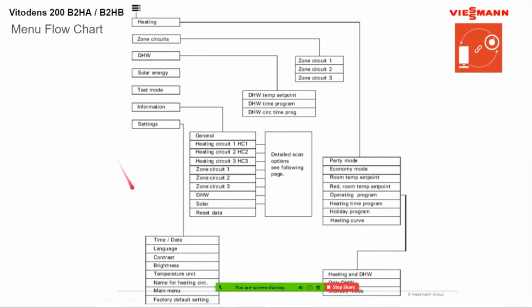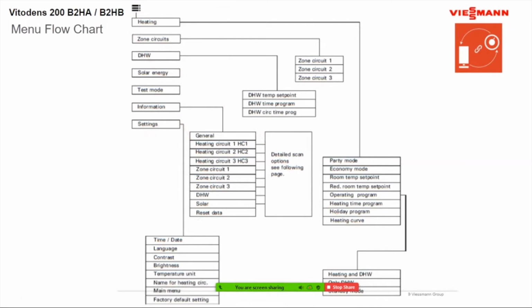And now you can see your time and date, your language, your contrast, your brightness, your temperature unit. And that's where you would change from Fahrenheit to Celsius, on that temperature unit. So this was the original way when this control first came out three or four years ago.